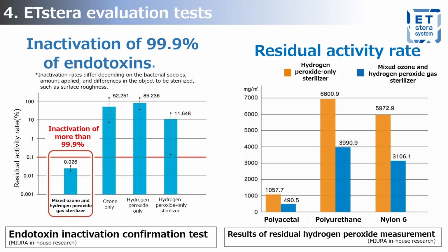The graph at right is a comparison of residual hydrogen peroxide in different materials when sterilized solely with hydrogen peroxide and when sterilized with mixed gas. Lowering the amount of hydrogen peroxide used leads to less residual hydrogen peroxide, reducing the effect on equipment and operators.